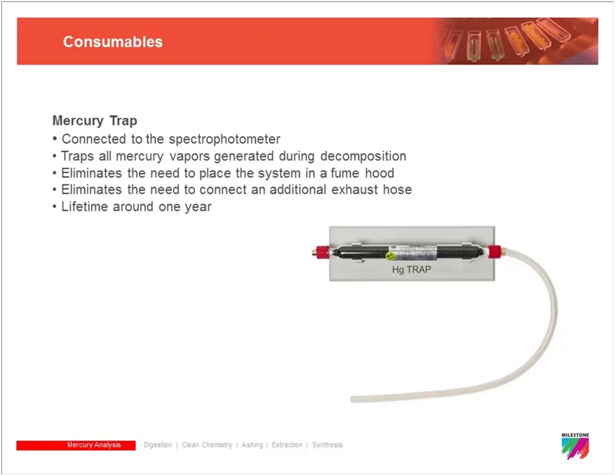And the last part of the system that I didn't mention in the schematics: after the mercury is carried through the spectrophotometer cell, it is collected on an activated charcoal trap. So all of the mercury that's released from your sample and analyzed is then collected on this charcoal trap. So there's no waste generated by the system that is not collected, which means you don't have to have a dedicated hood space to vent the system into. All of your mercury is collected on this charcoal trap, and they're replaced about once a year.